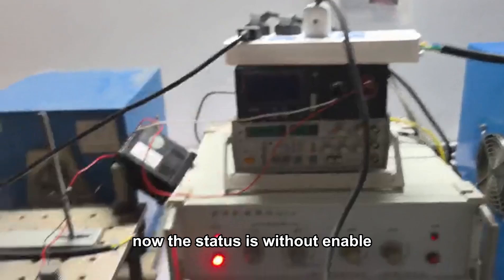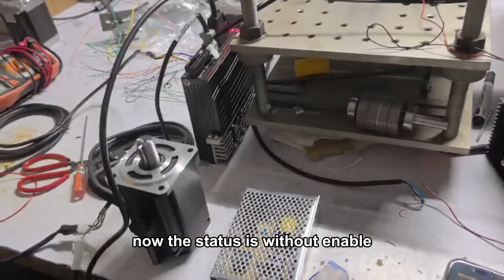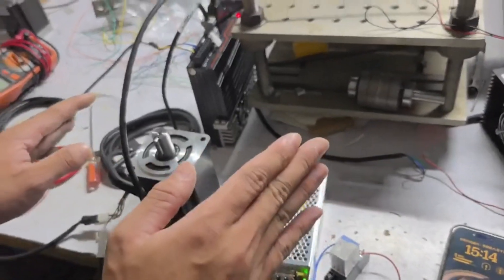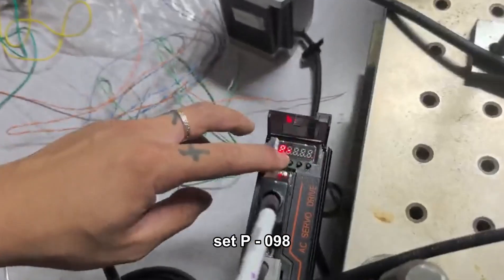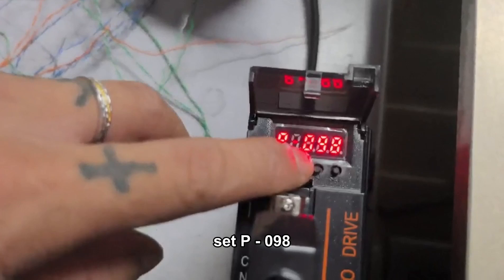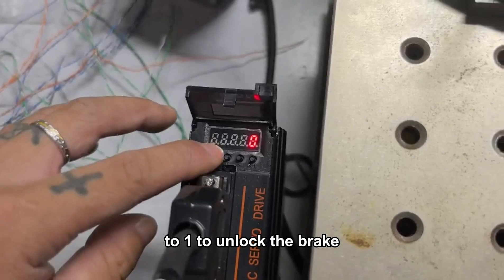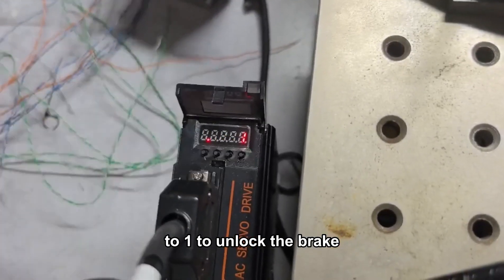Then we power on. Now the status is without enable, so we need to set the motor to enable. Set P098 to 1 to unlock the brake.